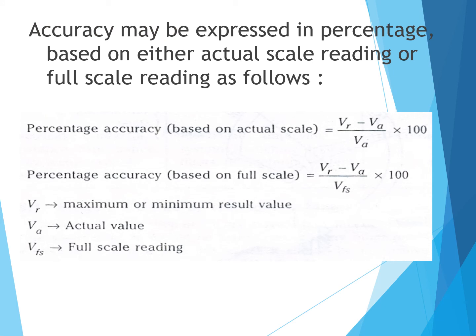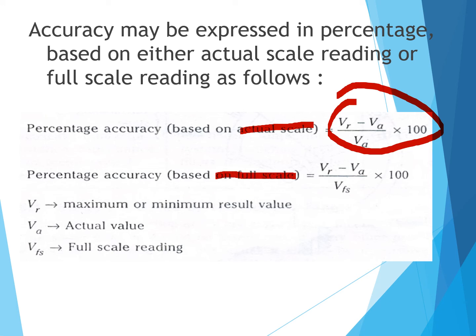Accuracy may be expressed as a percentage based on either actual scale readings or full scale readings. For actual scale: percentage accuracy = (VR − VA) / VA × 100, where VR is the maximum or minimum result value and VA is the actual value. For full scale: percentage accuracy = (VR − VA) / VFS × 100.